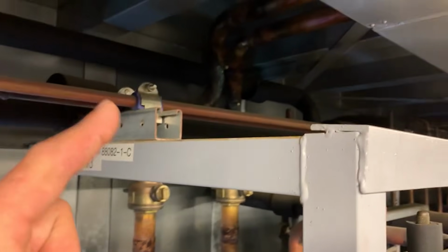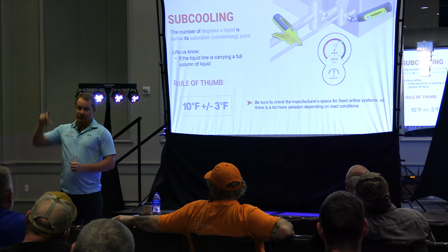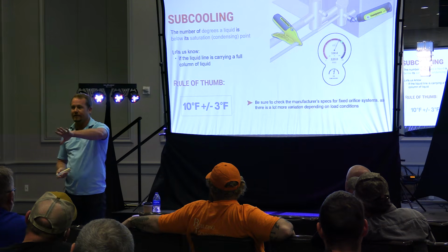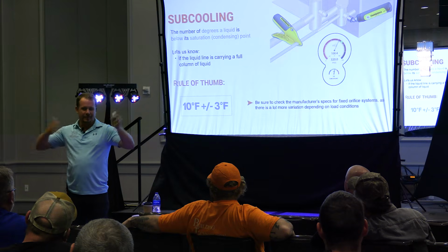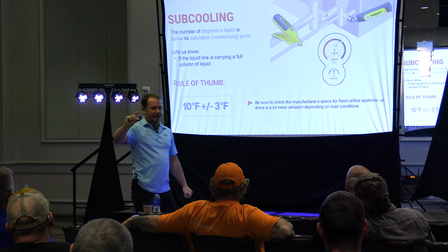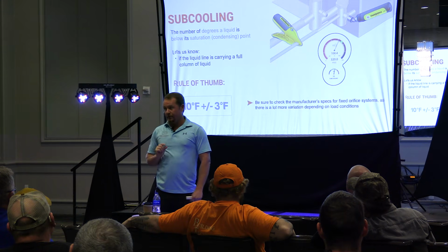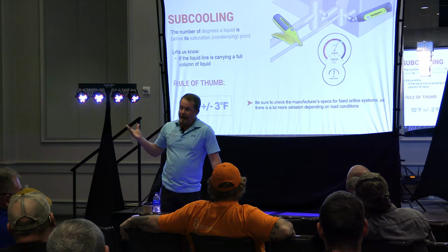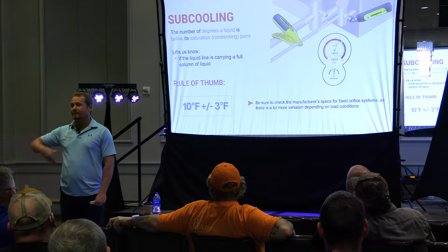Well now, yes, because now when it goes to that evaporator coil, it takes less energy to change it initially to flash it off. You know how we say, some of you have heard, when a liquid goes into the evaporator coil, it immediately goes to 30% vapor, 70% liquid, some version of that. If you cool that liquid down more, then you lose less to flash gas conversion as a percentage. So is that something that you could do? Sure, we don't in air conditioning much, but you could. So when people say that, sometimes that's what they're talking about.